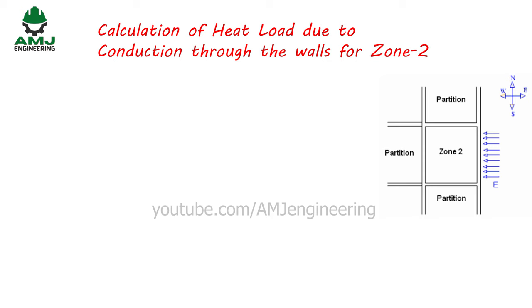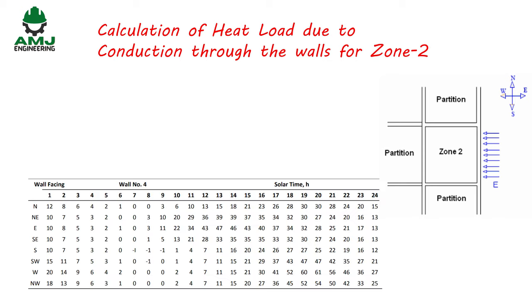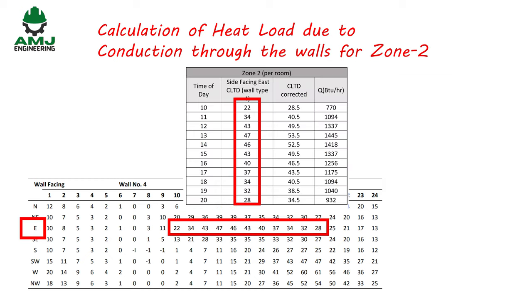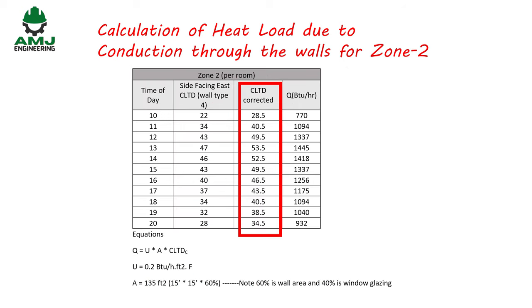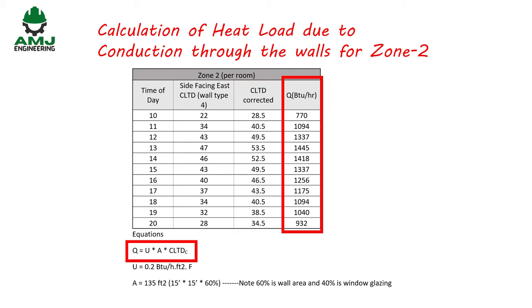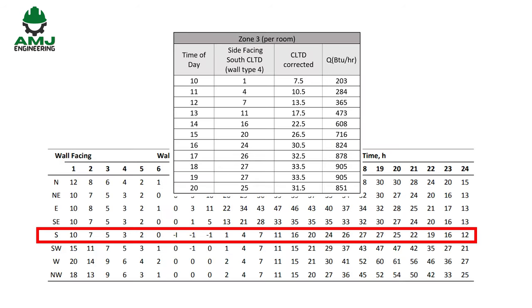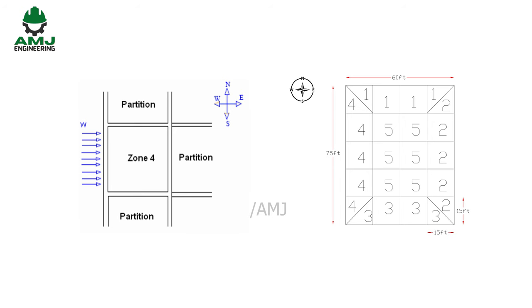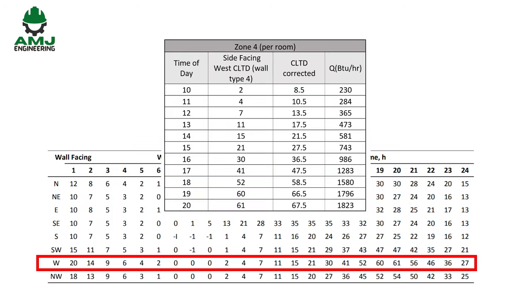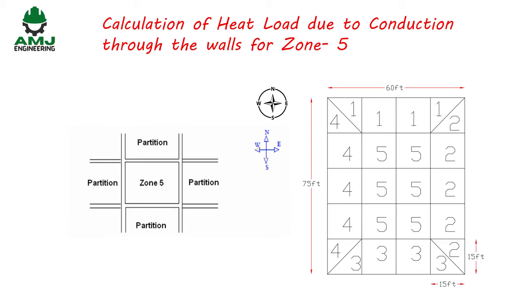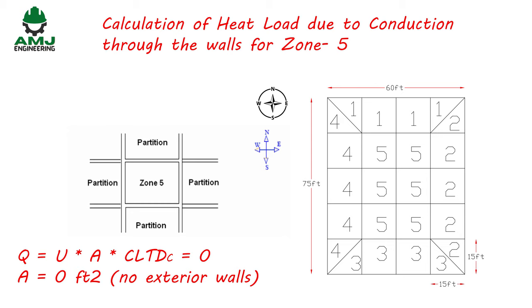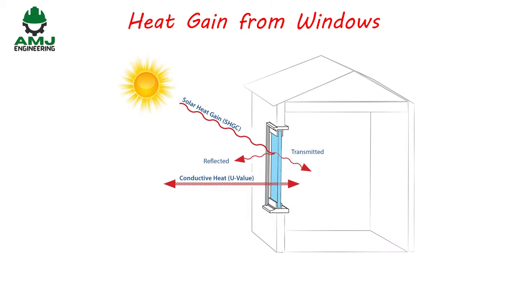For Zone 2, external walls face east, so east-facing CLTD values from wall type 4 are used. The same procedure applies for Zones 3 and 4, using south and west-facing CLTD values respectively. Zone 5 is an internal zone with no solar exposure, so the heat load due to conduction through walls is zero.